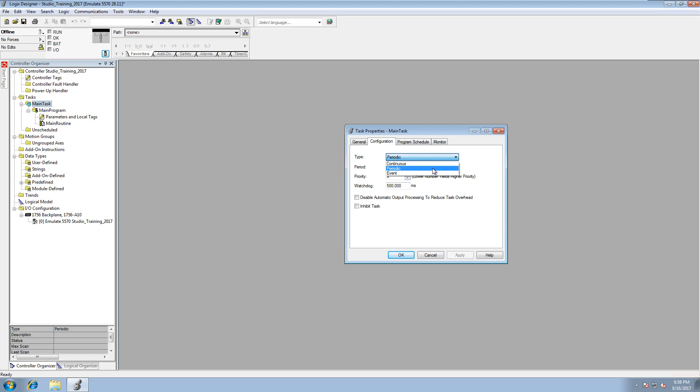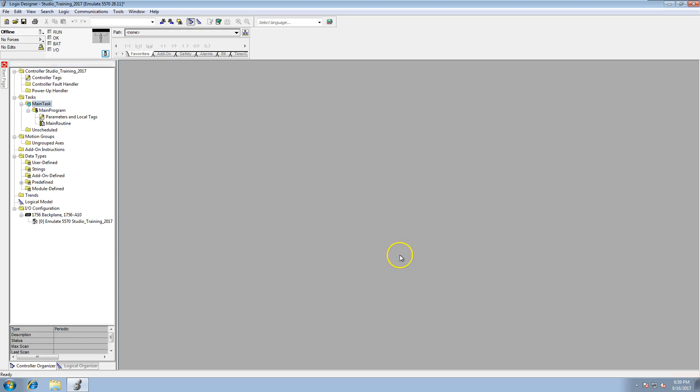So I can have several different things in my I/O tree, or basically several different tasks, and put the most important stuff at a lower rate if I want a high-speed system, or some of the stuff I'm not really worried about in a higher scan rate. So I'd like to point that out—that's the differences. And the event-driven, that's basically you would drive that off of another logic and not use that task until you actually tell it to based upon logic. We'll break that down in further training videos, but in this video I just want to kind of break down the continuous, the periodic, and the event. Again, we've chosen the periodic, and the reason behind that is because I want to control—once we get so big, I want to be able to control different sections of it.